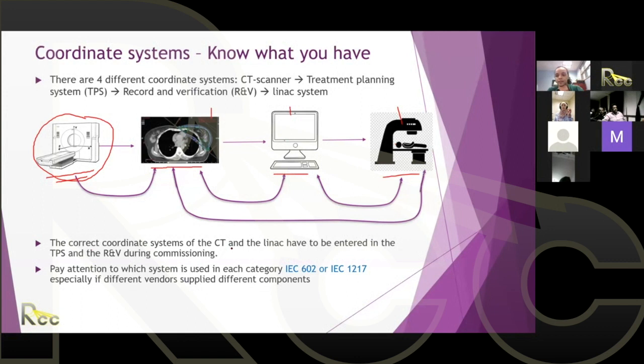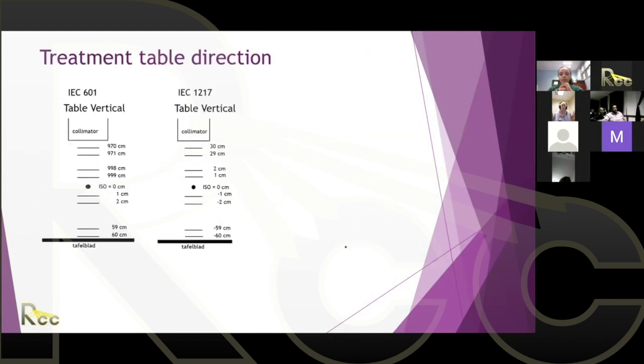This is really important for physicists, and also radiation oncologists should know, especially the head of department, because you have to know what's going on in your clinic. The two systems we're talking about regarding medical devices are IEC 601 or IEC 1217. IEC is short for International Electrotechnical Commission, and they set the standards for the devices, including the coordinate system. So both systems are equal - there is no one better than the other.